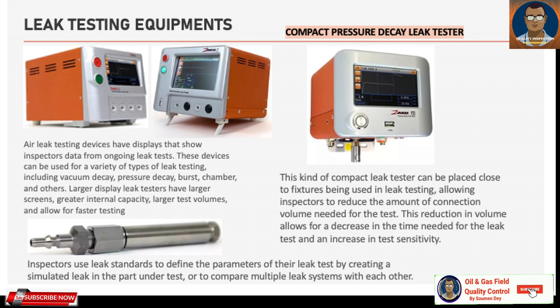Let us have a look at some leak testing equipment. Air leak testing devices have a display that shows inspector data from ongoing leak tests — you can see these pictures within the slides. These devices can be used for a variety of leak testing types, including vacuum decay, pressure decay, burst, chamber, and others. Larger display leak testers have larger screens, greater internal capacity, larger test volumes, and allow for faster testing. The compact pressure decay tester can be placed close to the fixture being used, reducing the connection volume needed, which decreases test time and increases test sensitivity.